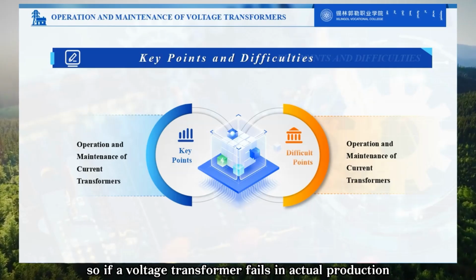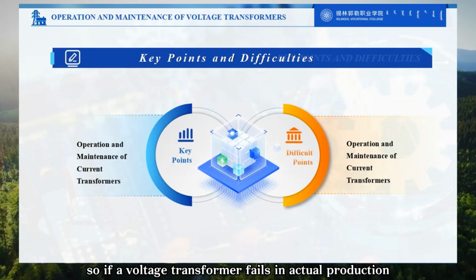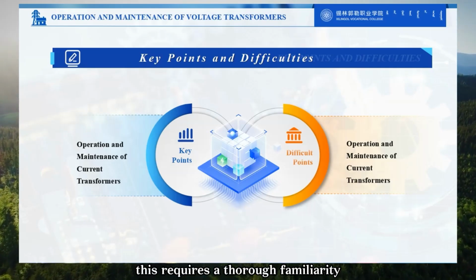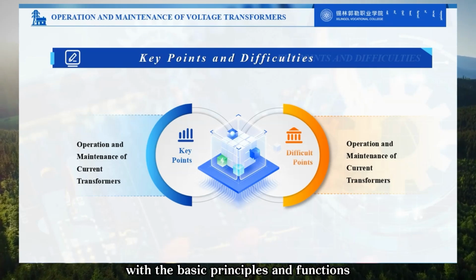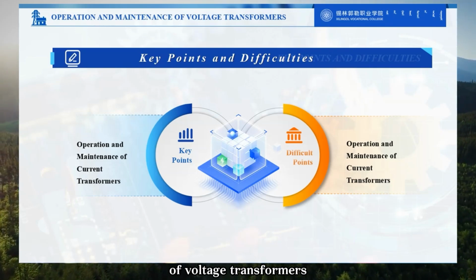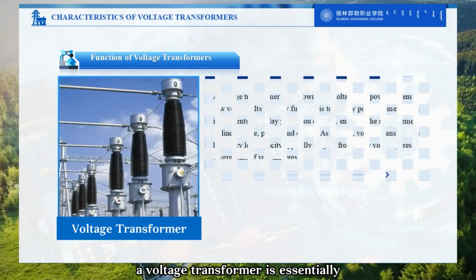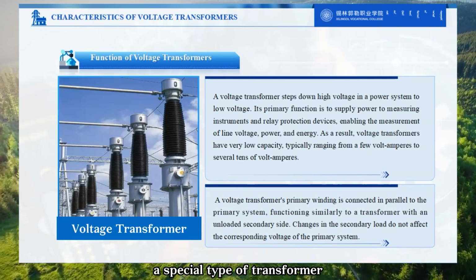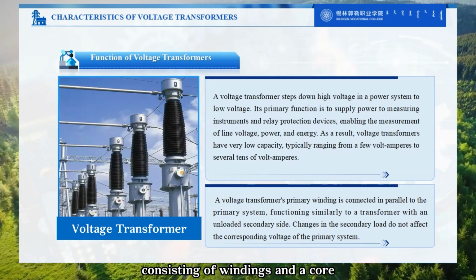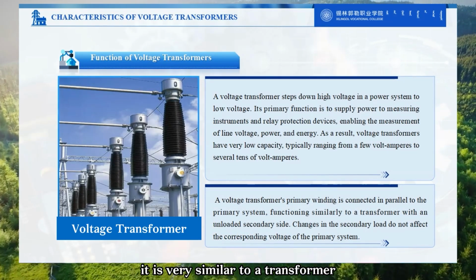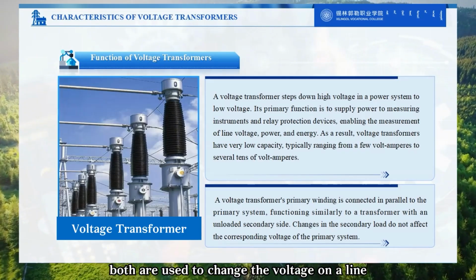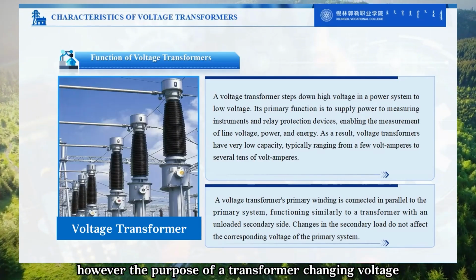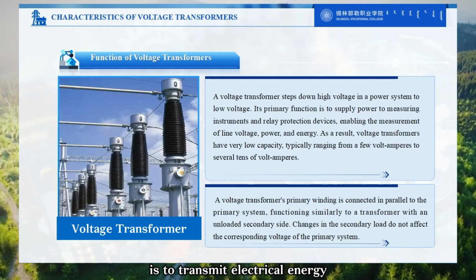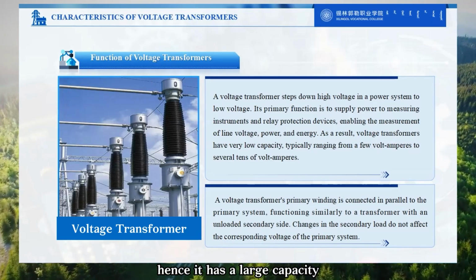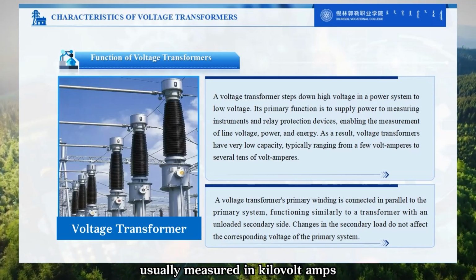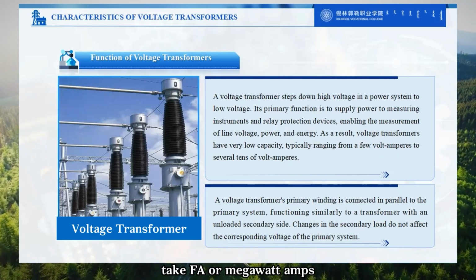So if a voltage transformer fails in actual production, how should we maintain it? This requires a thorough familiarity with the basic principles and functions of voltage transformers. A voltage transformer is essentially a special type of transformer consisting of windings and a core. It is very similar to a transformer. Both are used to change the voltage on a line. However, the purpose of a transformer changing voltage is to transmit electrical energy. Hence, it has a large capacity, usually measured in kilovolt-amperes (kVA) or megavolt-amperes (MVA).